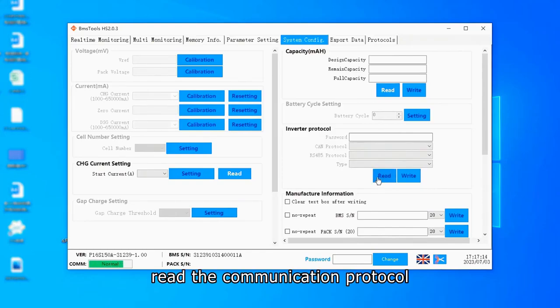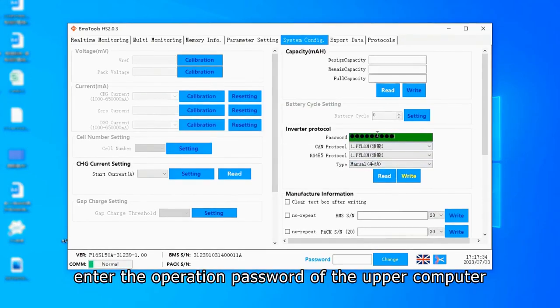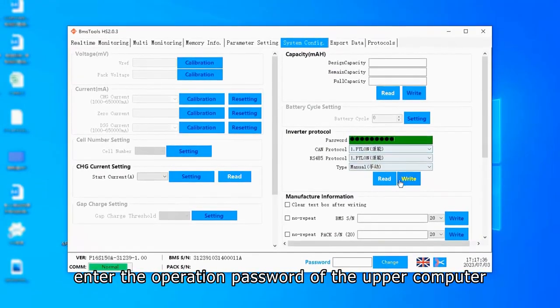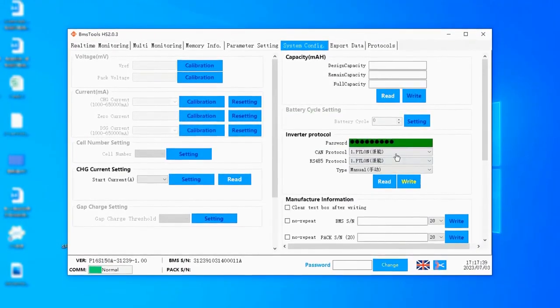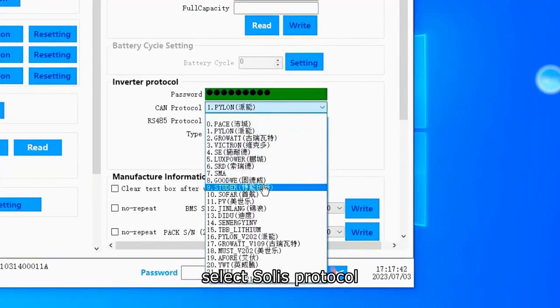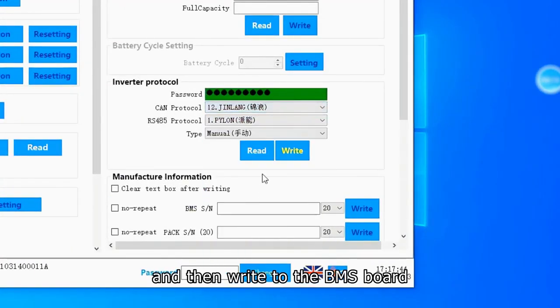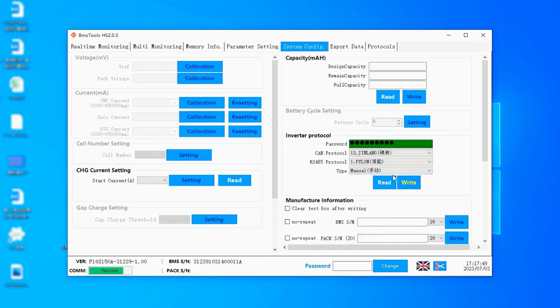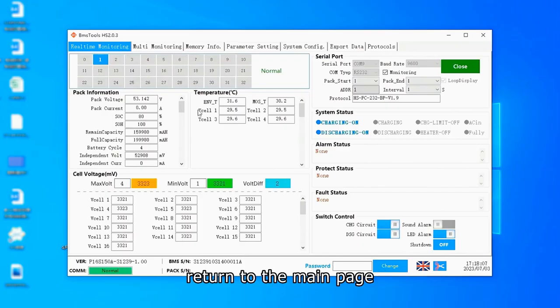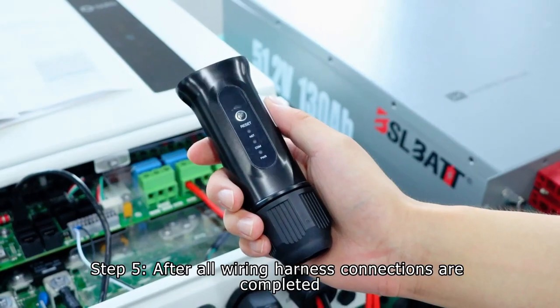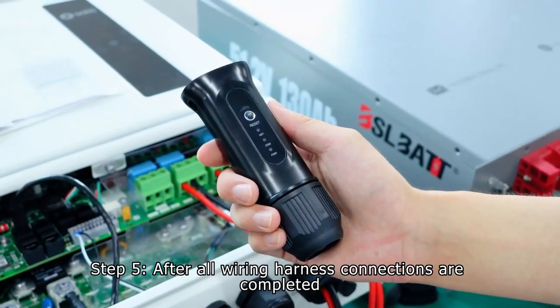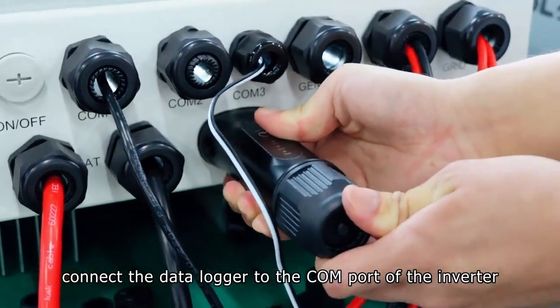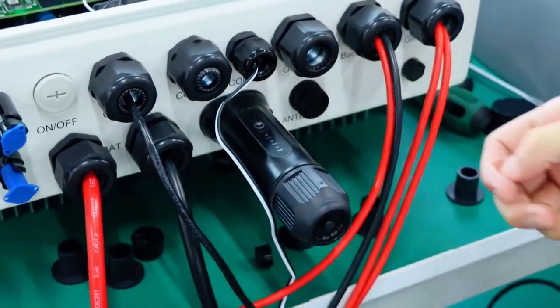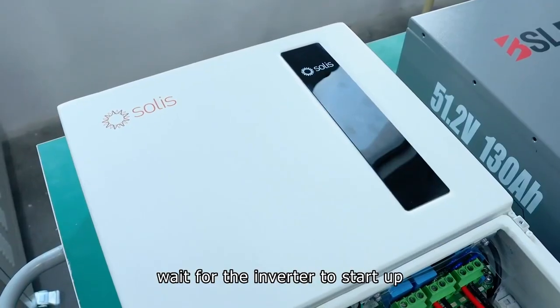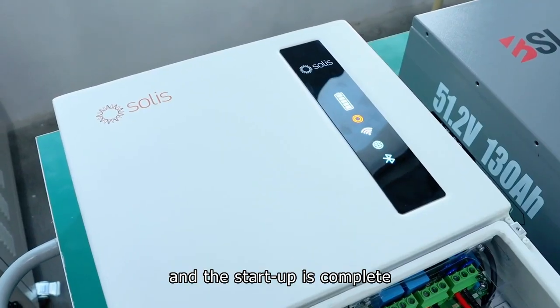Then select System Settings. Read the communication protocol. Enter the operation password of the upper computer. Read again. Select Solis protocol, and then write to the BMS board. After the operation is completed, return to the main page. Step 5. After all wiring harness connections are completed, connect the data logger to the COM port of the inverter. Then turn on the power grid, wait for the inverter to start up, and the startup is complete.